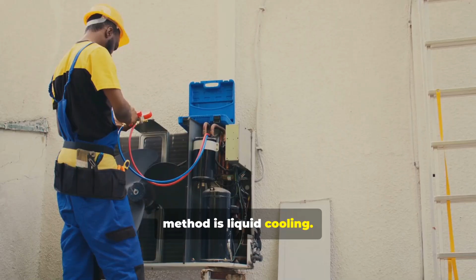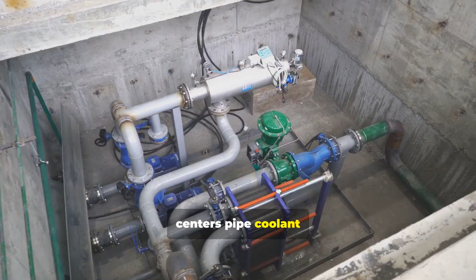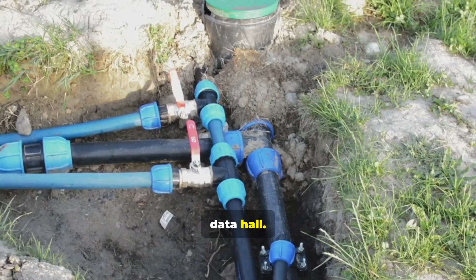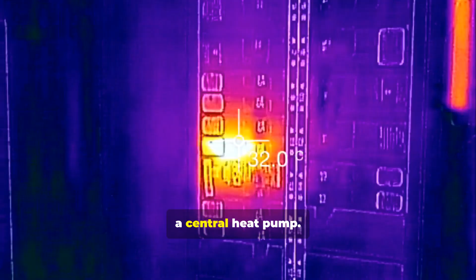The first step is collecting heat directly from the servers. The most efficient method is liquid cooling. Instead of just blowing air across components, advanced data centers pipe coolant to server racks or to individual chips. This liquid absorbs thermal energy far better than air. The warm water, now carrying waste heat, is piped out of the data hall. Arrows from server racks to pipes carrying low-grade warm water, 35 degrees Celsius, to a central heat pump. This water is low-grade, between 30 and 40 degrees Celsius, 86 to 104 degrees Fahrenheit. It is warm but not hot enough for building radiators.